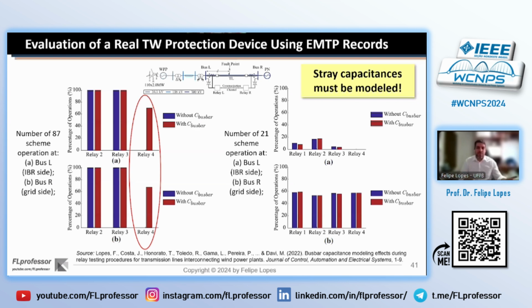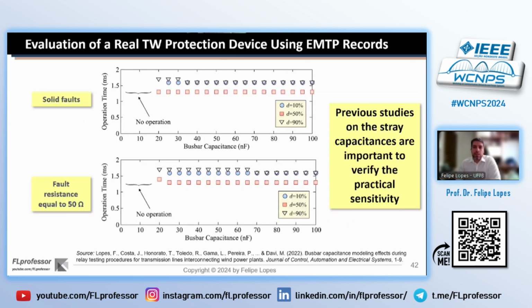We only do not model it when we are considering conventional phasor protections, for instance. And by modeling the busbar capacitance, we could see in this paper that the traveling wave protection operated as expected, unlike the other elements, which are based on quantities other than traveling waves and present the same behavior without and with busbar capacitance. It shows that stray capacitance must be modeled if you are interested in testing real traveling wave protection devices in this type of system that interconnects IBRs.